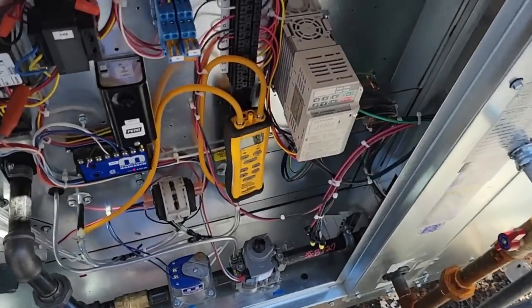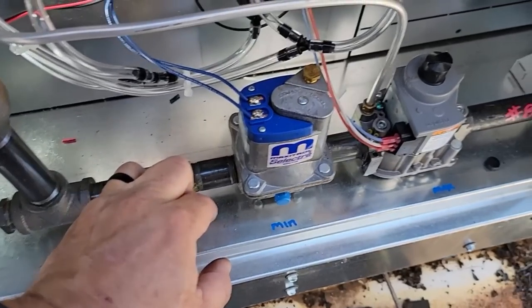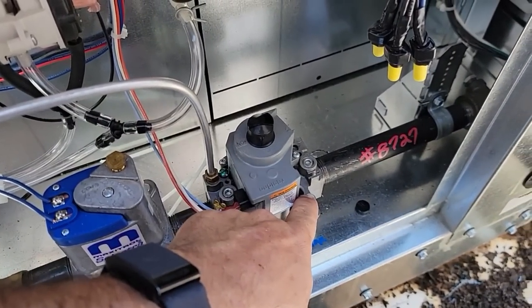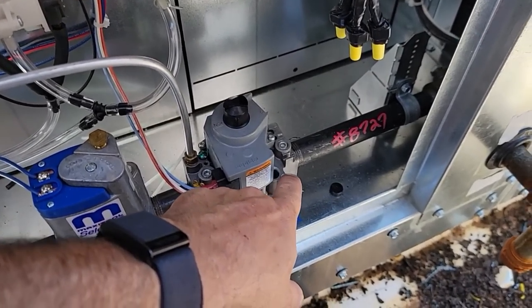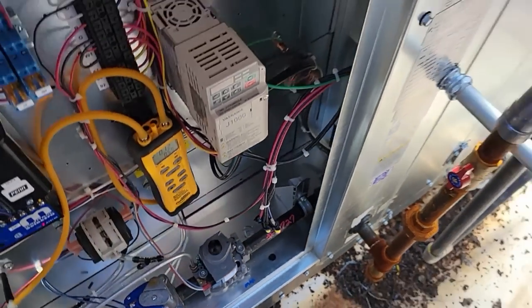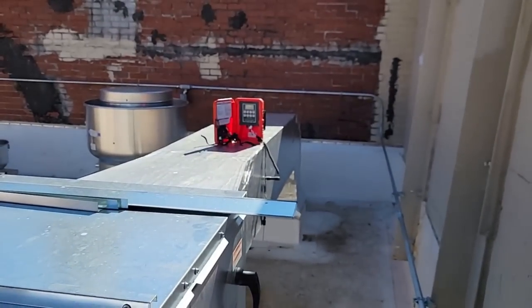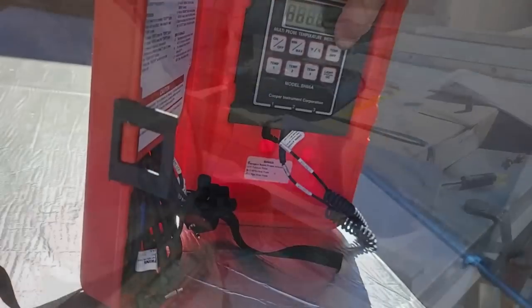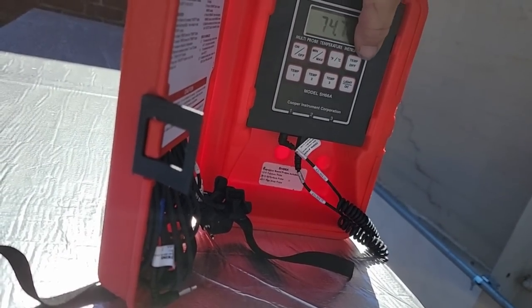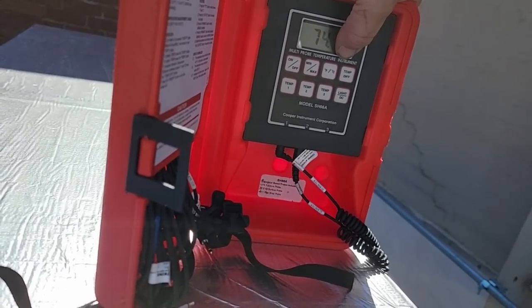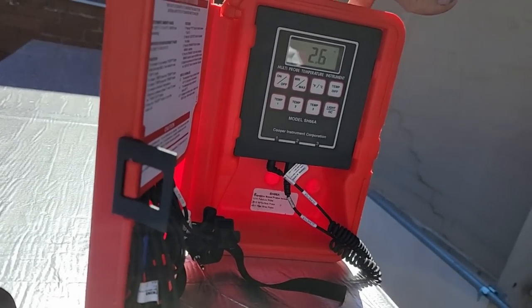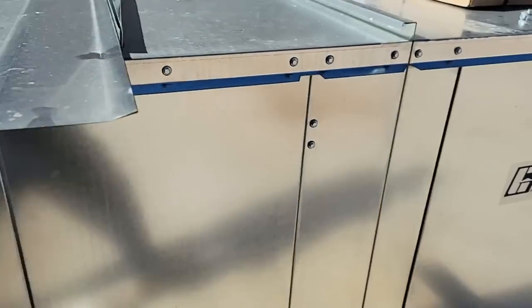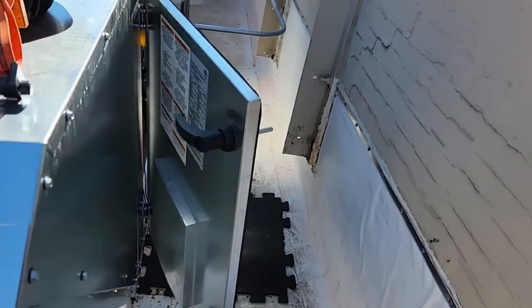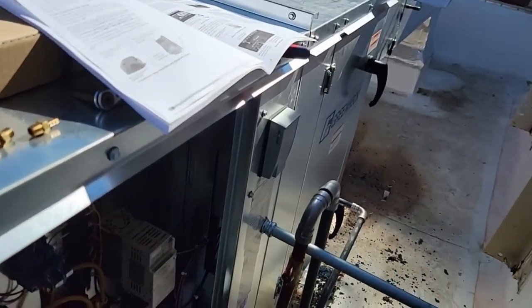So we've done that. We're going to open up our main valve here, and then we're going to adjust our gas pressure back up. I took it out so that we wouldn't overheat the building any quicker than we needed to. Go ahead and put this on differential down here. Set it up for a 70 degree differential. So we'll go in here and go to differential. Right now it's about a 2 degree differential between the two, which I don't have the probe in the end, but it's in the shade just like this is in the shade. I'm not horribly worried about it.